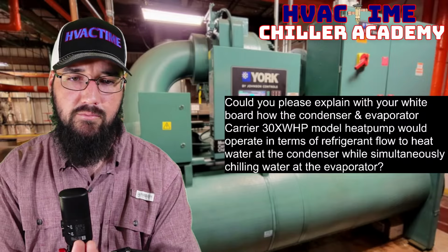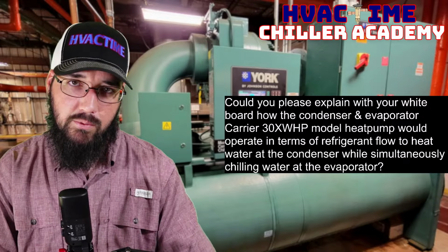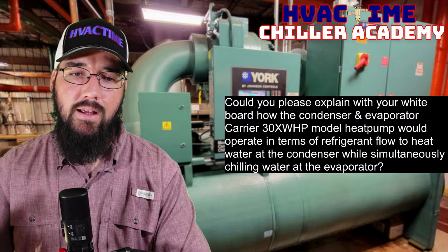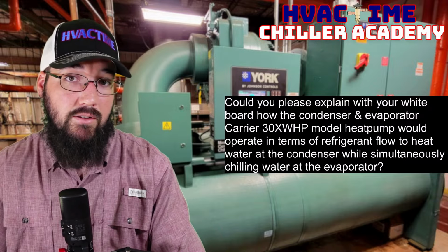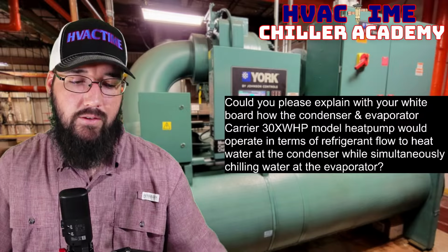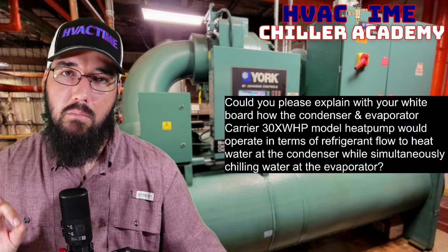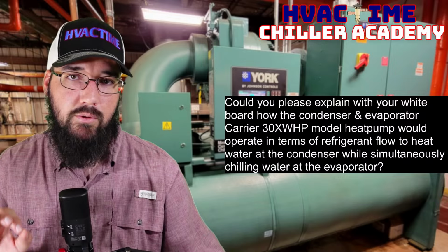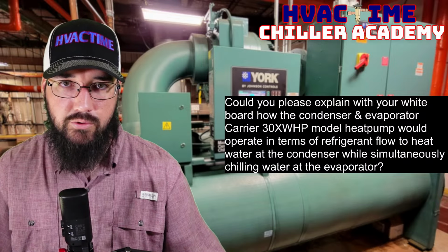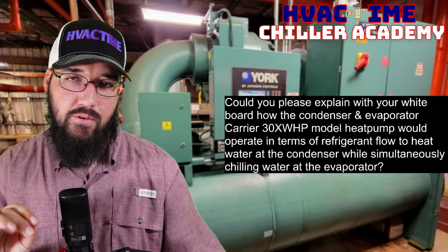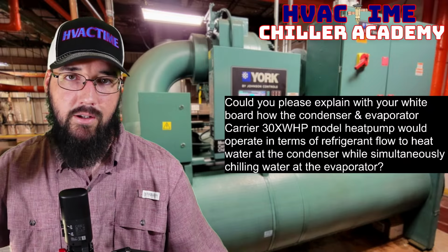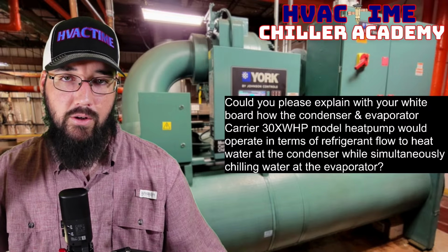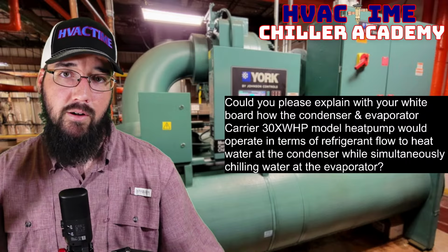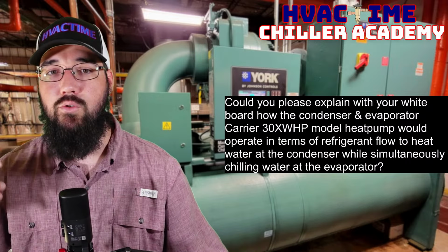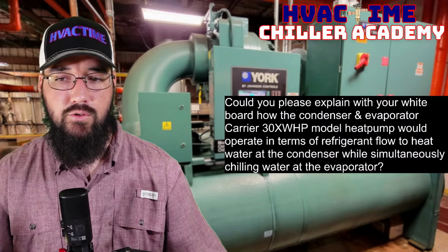So that is our basic high level of how this specific machine is configured, how that refrigerant circuit works, and how I would expect it to operate. Most of what I'd be troubleshooting is going to be relatively similar to any other troubleshooting I would do, except that I would keep in mind the elevated condenser head pressures and water temperatures. That's going to be the primary difference for this machine compared to other styles of chill water systems.